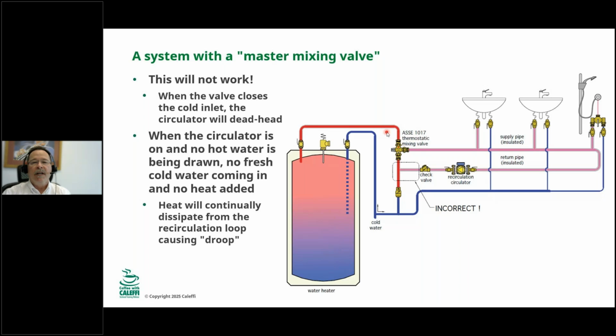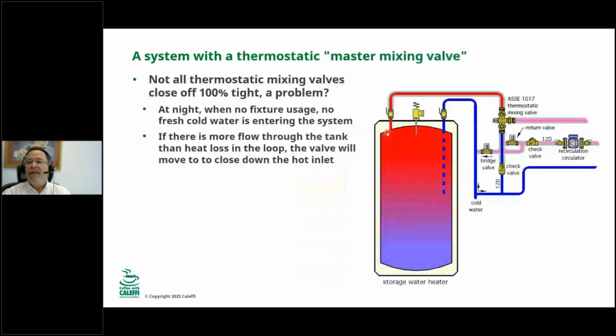Another thing to talk about is something called temperature creep. Let's talk about that a little bit. If you have a thermostatic mixing valve that does not close this hot inlet port 100%, that can be a problem. Not always, but it can be. Let me talk about that. So again, at night when there's no fixture usage, there's no fresh water coming into the system, right? The only time fresh water comes into the system is when you open a fixture. Otherwise, it's a closed loop system. You can think of it that way.